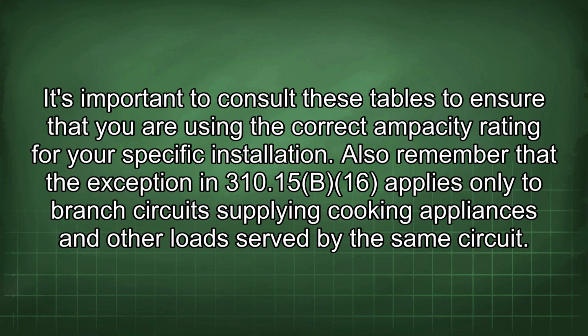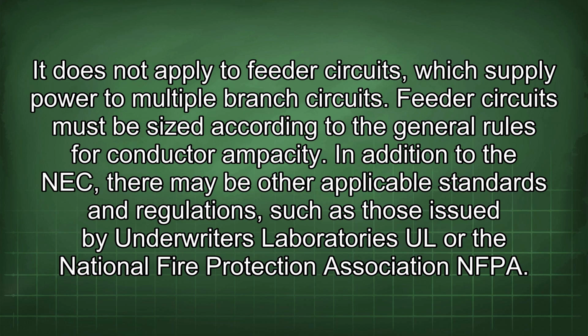Also remember that the exception in 310.15(B)(16) applies only to branch circuits supplying cooking appliances and other loads served by the same circuit. It does not apply to feeder circuits, which supply power to multiple branch circuits. Feeder circuits must be sized according to the general rules for conductor ampacity.